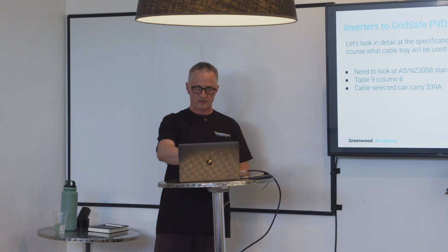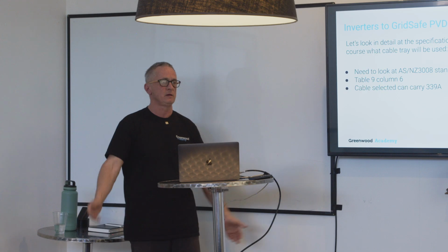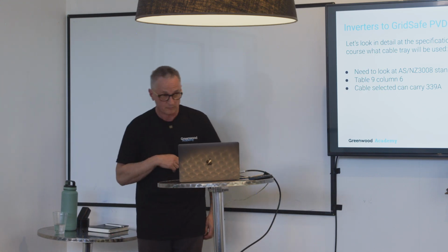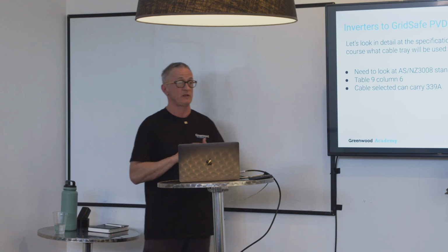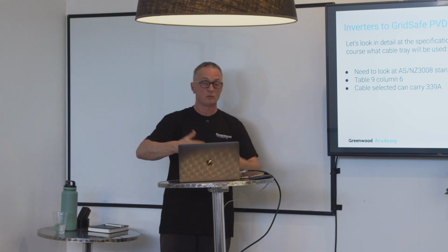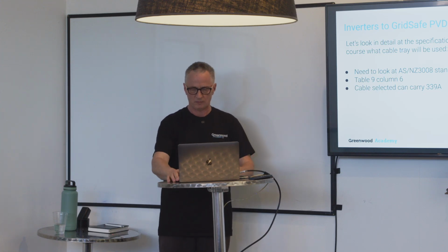And this is where someone who hasn't done the commercial goes, oh, well, it can carry heaps. I mean, what's a SunGrow inverter output? About 159, 160 amps, right? And of course, then you have to apply the 1.25 rule, but the reality is that's what it's outputting. And we'll talk about that relationship.